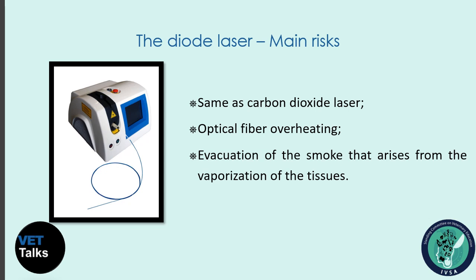Like the carbon dioxide laser, the diode laser also has associated risks, and they are basically the same as the carbon dioxide laser. Additionally, there is optical fiber overheating, which can be avoided by the use of fluid or by reducing the exposure time to 3 seconds per pulse, because the overheating of the optical fiber can damage it and destroy it, and we can't use it anymore.